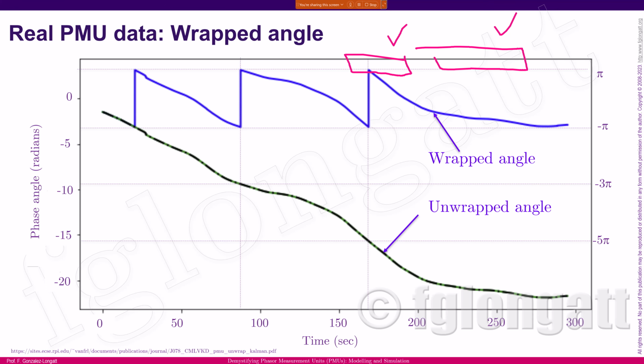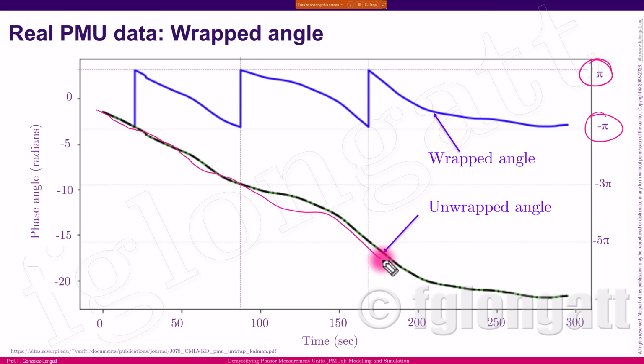I was telling you that with PMU data, the data streams follow what we call the wrap angle. What does the wrap angle mean? It means that when measuring phasors, they are restricted to an angle from pi to minus pi, or in other words, 180 degrees to minus 180 degrees. However, in offline simulation the angle typically keeps growing or decreasing and never follows that wrapped pattern.